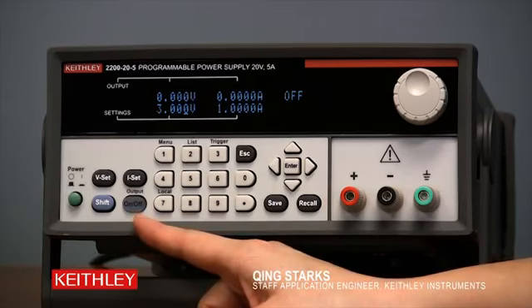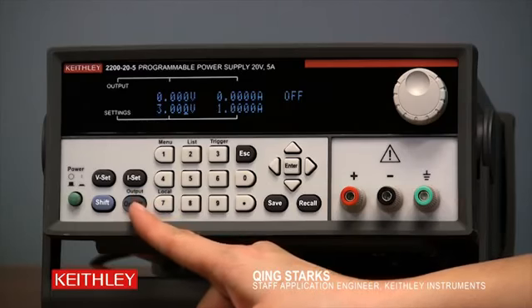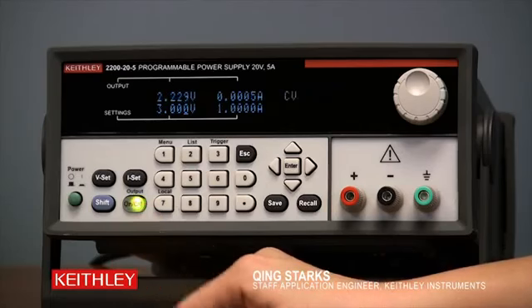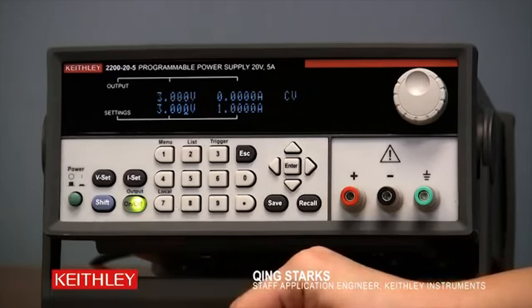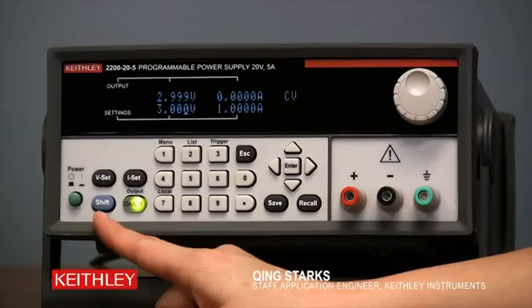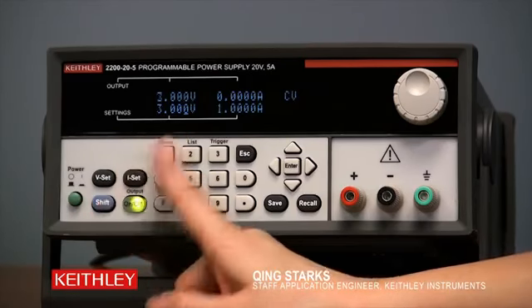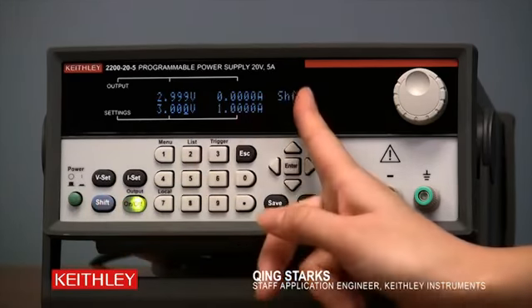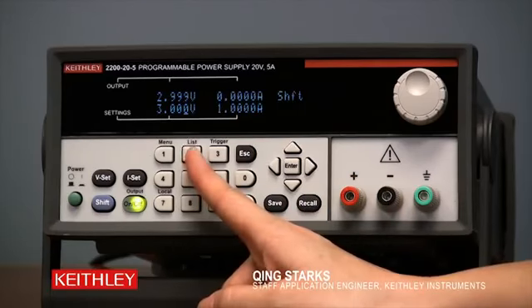To run the list, we'll press the output on/off button first to turn on the output. So press output on and off. Now the light is lit. And then we have to initiate the list by pressing Shift and List. Shift, now the display is showing shift, list, which is numeric keypad 2.